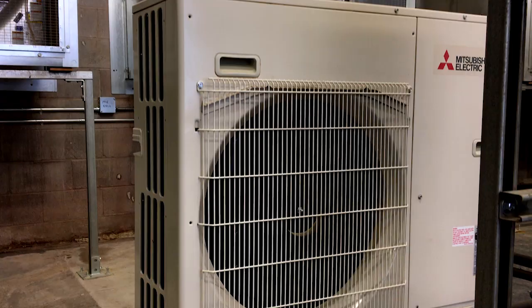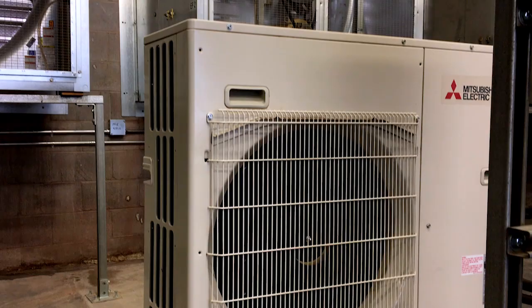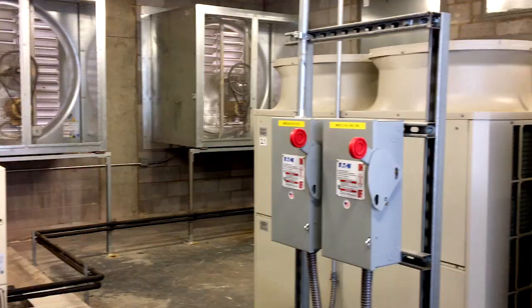They're a perfect match for existing buildings, older buildings, where we do not have a lot of space to run ductwork or mechanical systems. We're able to move energy through two smaller pipes as opposed to big, large ducts. This building in particular, when we finished with the installation, we have a lot of surplus space that was previously occupied by ductwork and air handlers.